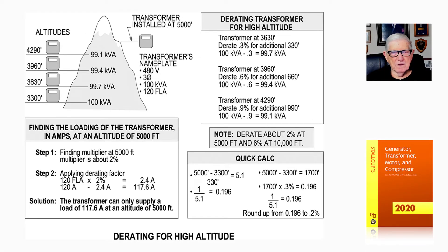Let's take a look at Figure 7-13, derating for high altitude when you install the transformer at 5,000 feet. The drawing shows the transformer installed at 5,000 feet. The transformer's nameplate would have 480 volt 3-phase 4-wire, 100 kVA, 120 FLA when you do your math.